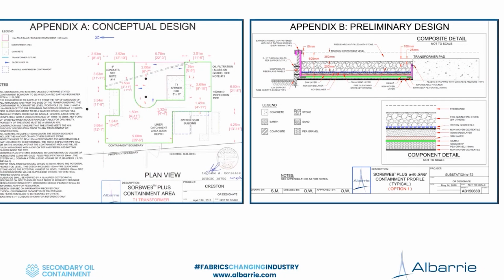The other one is just showing you an above grade option. In this case, we cannot build a containment below grade for a number of reasons. It's also an existing substation. So the customer opted for building the containment above grade using an above ground composite support wall system. Here we build all the layers and have the water flow through the bottom on 50 millimeters of pea gravel, and then it just gets discharged onto the surface of the substation.